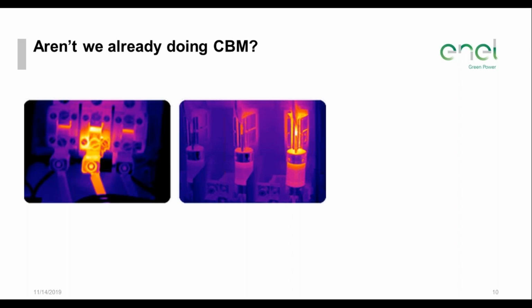In this case, it's clearly showing overheating of some power connections. Thermography is actually one of the most common condition-based maintenance technologies, where we can see the incoming of a failure before it gets catastrophic. Some may argue it's a late notice, because if something is hot, we're not that far away from the failure, but by all intents and purposes, it is a condition-based maintenance technology.